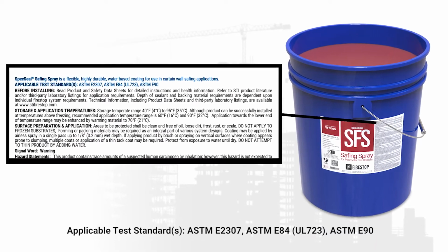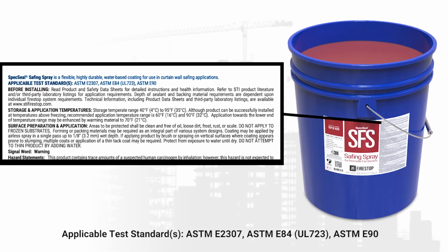It should go without saying that the specific fire-stopping product being installed is absolutely critical, as is the installed amount, depth, and location. There are many different products that look similar. They may even be red. And you'll want to verify that the supplied products have labels from recognized quality assurance agencies. For penetrations, you're going to want to look for ASTM E814 or UL 1479 on the label.